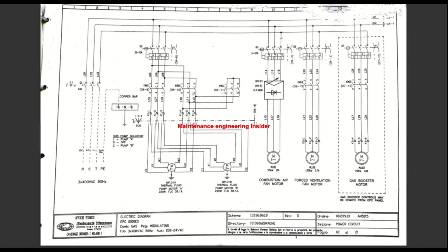If you start it to go star-delta, this one will be running. If you switch on to this one, it will go star-delta and this one will be running. So if there's no power coming here, we want to see where the coil of these contactors is. These contactors here — we see that the coils are on the same page. This is on sheet number eight, section eight; this is on sheet number eight, section ten; this is on sheet number eight, section line eleven.